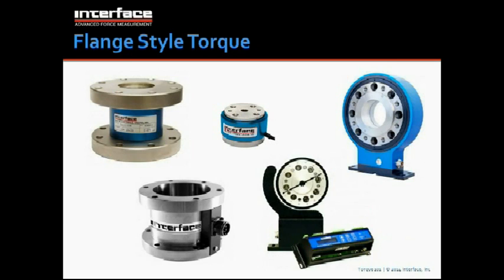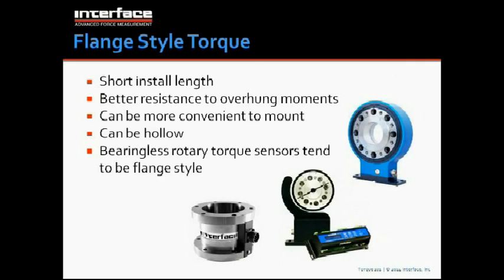These are some examples of flange style sensors, and they have a short length. They have better resistance to overhung moments. Imagine if you have the weight of a motor or something hanging on the sensor. The shorter the sensor is, the less bending you have in the sensor. They can be hollow. Sometimes people like to have hollow sensors to run hydraulics or thermocouple wires or some kind of electrical lines through the center of the sensor. A hollow sensor can accommodate that. Bearingless rotary torque sensors also always tend to be flange style, with few exceptions.